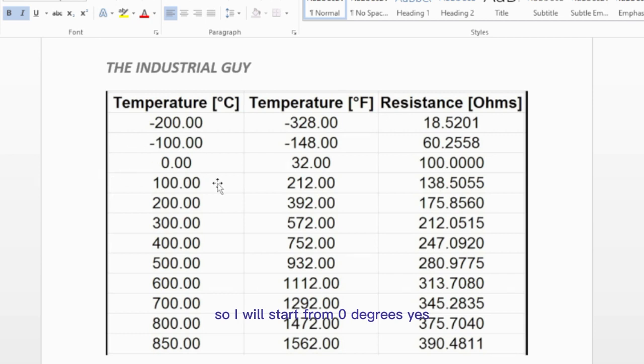So I will start from 0 degree Celsius. If we are using PT100, at 0 degree centigrade the PT should give us a value of 100 ohms. At 100 degrees centigrade, PT should give us a value of around 138.50 ohms. Same if we're interested in degree Fahrenheit - at 212 Fahrenheit, the resistance is 138.50, etc. This is how we read the chart of PT100.